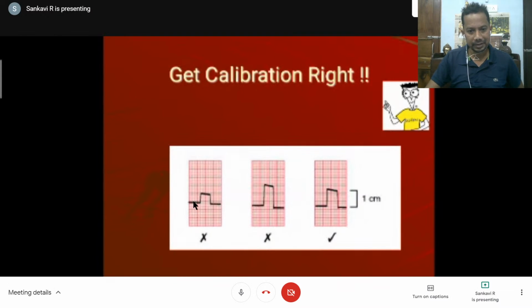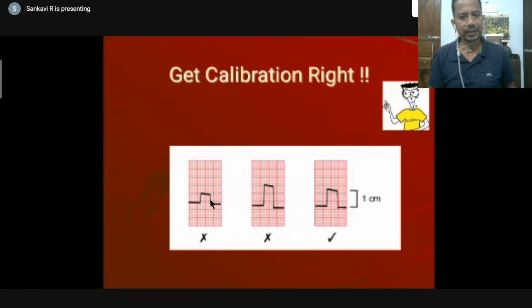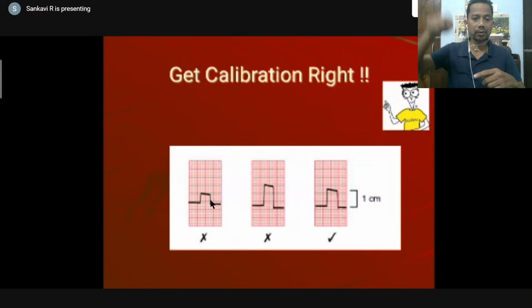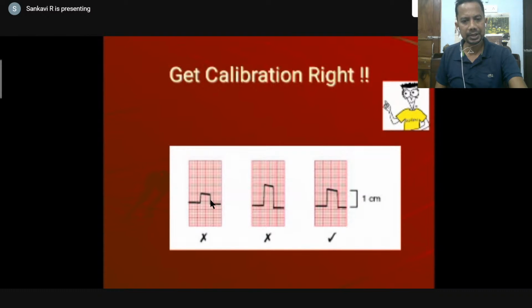Also, in this calibration, this is 5 small squares in height. Now what has happened here is, let us say this patient had HOCM, hypertrophic obstructive cardiomyopathy, and the machine sensed that the R wave amplitude is larger than the width of the paper, so it will go very high and the stylus will bypass the paper. So automatically, as it's a computerized thing, it will halve the calibration. When the machine senses that the electrical activity is bypassing the paper, it will halve the calibration. Now say in lead V5 or V6, the R wave was 20 small squares in height and the calibration is 5. So actually the R wave is 40. You have to double it. So you have to calculate for a calibration of 10 small squares in height.